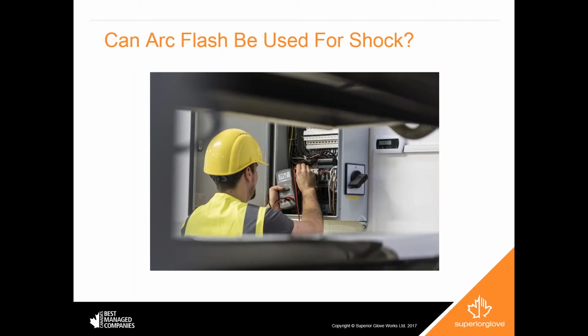at all. And the other thing to, I think, mention here is that most people have had the understanding that if you were below 240 volts of electricity, you didn't have to really worry about it. But the actual standard now states that anything at 50 volts or more should be treated and tested as though arc flash was certainly a possibility, because it can happen at lower levels than 240 volts.